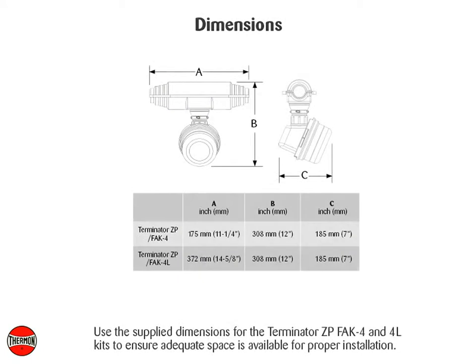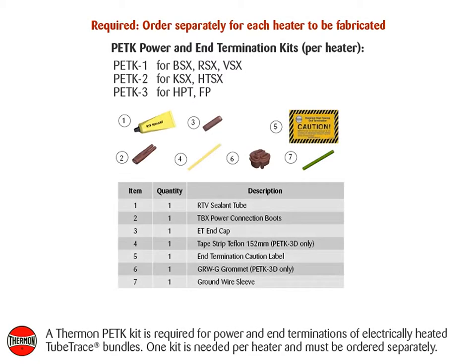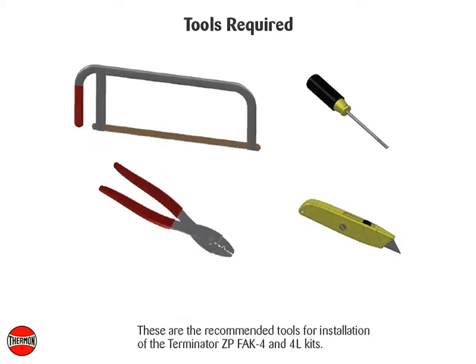Use the supplied dimensions for the Terminator ZP, FAK-4, and 4L kits to ensure adequate space is available for proper installation. A Thermon PETK kit is required for power and end terminations of electrically heated tube trace bundles; one kit is needed per heater and must be ordered separately. These are the recommended tools for installation of the Terminator ZP, FAK-4, and 4L kits.